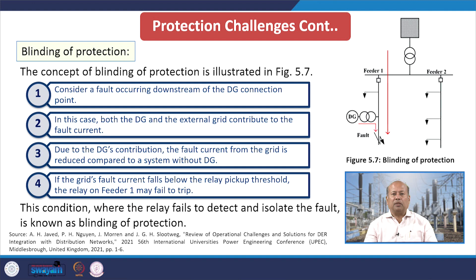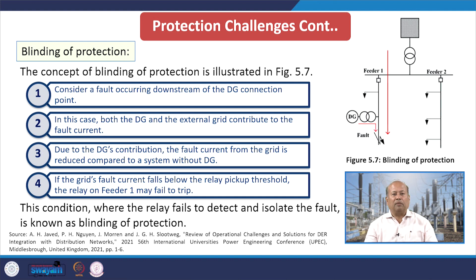In case of blinding of protection, as seen from diagram 5.7: it considers a fault occurring downstream of the DG connection point. Both the DG and the external grid contribute to the fault current. Due to the DG's contribution, the fault current from the grid is reduced compared to a system without DG. If the grid's fault current falls below the relay pick-up, the relay on feeder 1 may fail to trip. This condition — where the relay fails to detect and isolate the fault — is known as blinding of protection.